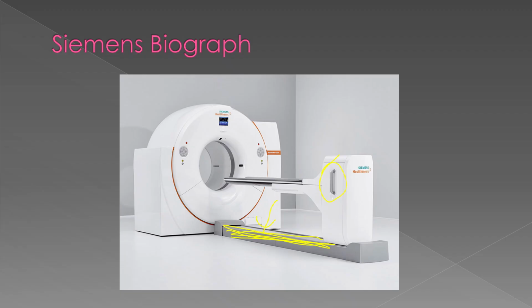Here's the laser pointers I told you about. There's one on the top and one on the sides. You want to make sure that the patient is in the center of the useful field of view. And then you have over here the controls. There's an e-stop button on each side.